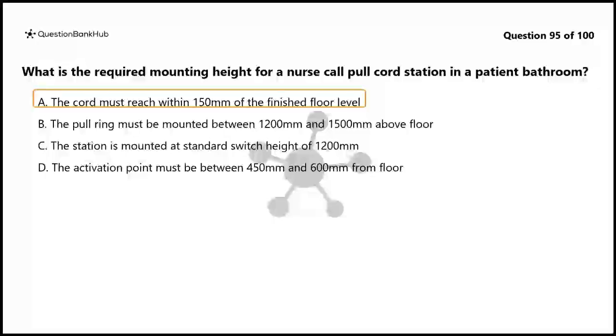The correct answer is A. The cord must reach within 150 mm of the finished floor level. Nurse call pull cord stations in bathrooms must have the cord extending to within 150 mm, 6 inches, of the finished floor. This allows a patient who has fallen to reach and activate the emergency call from floor level. The mounting height of the station itself is secondary to ensuring the pull cord reaches the required low point.